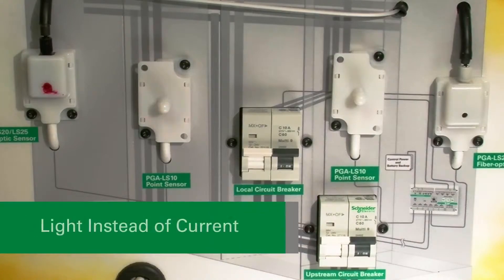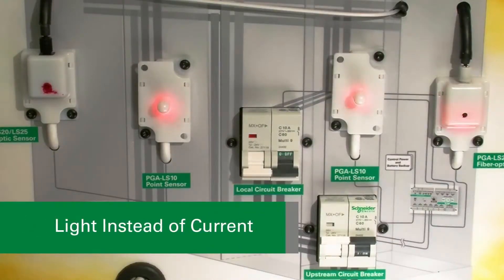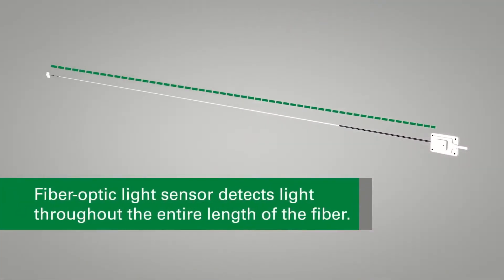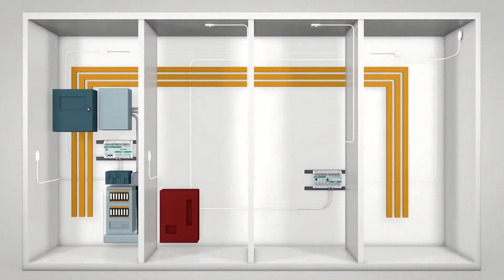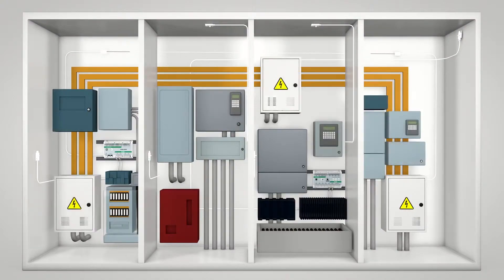Littelfuse's ArcFlash relays use light instead of current to detect an ArcFlash in under 1 millisecond. The fiber-optic light sensor detects light throughout the entire length of the fiber. The sensor is ideal to protect bus bars, multiple compartment installations like motor control centers, or areas with many obstructions.